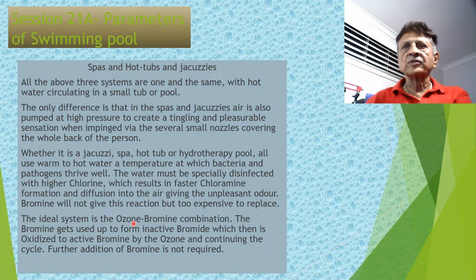The ideal system is therefore the ozone-bromine combination. The bromine gets used up to form inactive bromide. This inactive bromide reacts with ozone to form active bromine, and it continues as a disinfectant. So this continues to recycle. In other words, the bromine gets used to bromide, becomes bromine again because of ozone, and so on. Therefore, you may not need further addition of bromine, other than supplementing it when it is lost through sprays and, if there is a filter, through filters.